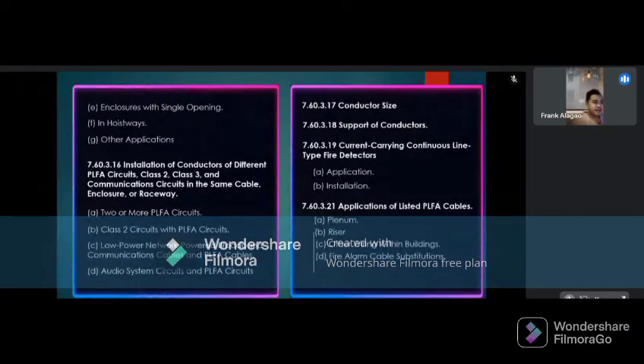So power limited fire alarm circuit conductors entering a compartment, enclosure, device box, outlet box, or similar fitting shall be permitted to be installed with electric light, power, class 1, non-power limited fire alarm, and medium power network powered broadband communication circuits where they are introduced solely to connect the equipment connected to the power limited circuits to other circuits controlled by the fire alarm system to which the other conductors in the enclosure are connected, where the power limited fire alarm circuit conductors must enter an enclosure that is provided with a single opening. So they shall be permitted to enter through a single fitting such as a tee, provided the conductors are separated from the conductors of other circuits by a continuous and firmly fixed barrier.